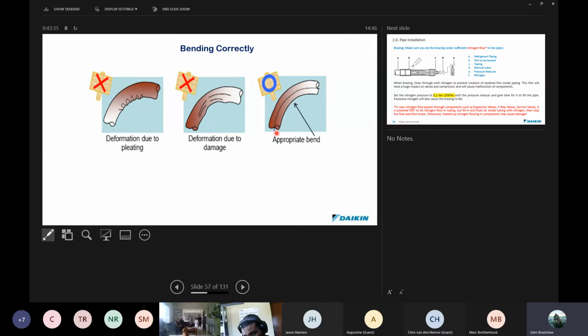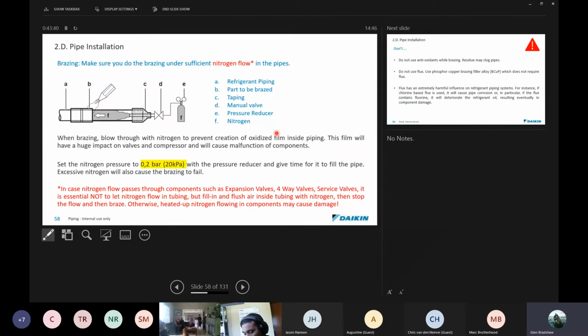So that's sort of working with piping. One of the other aspects of working with piping is that we are required to braze to join sections together. At any time that you braze on a refrigeration system, a VRV system included, you are required to use a flow of nitrogen through the piping, set up through a regulator at not more than 20 kPa, 0.2 bar. The rig, as you can see here, is a nitrogen bottle with a regulator, and we then have a reducer fitting onto it, and we blow nitrogen into the pipes, through the area that we're going to be welding, at a low pressure, not at a high pressure. We don't want that blowing back through the weld and damaging the weld. The piping must not be closed off on the end. The nitrogen must be able to flow out.